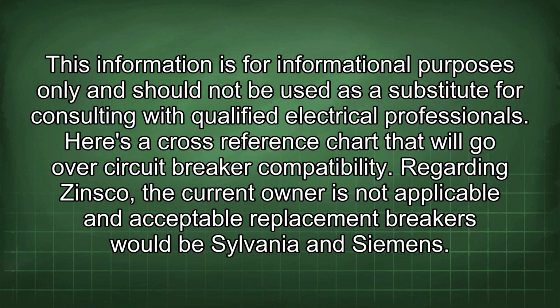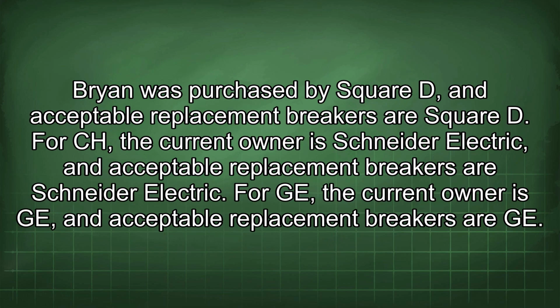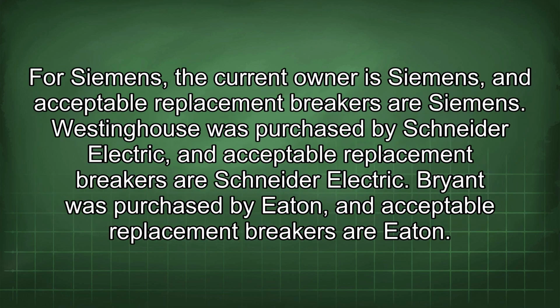Regarding Zinsco, the current owner is not applicable and acceptable replacement breakers would be Sylvania and Siemens. Brian was purchased by Square D and acceptable replacement breakers are Square D for CH. The current owner is Schneider Electric and acceptable replacement breakers are Schneider Electric. For GE, the current owner is GE and acceptable replacement breakers are GE. For Siemens, the current owner is Siemens and acceptable replacement breakers are Siemens.